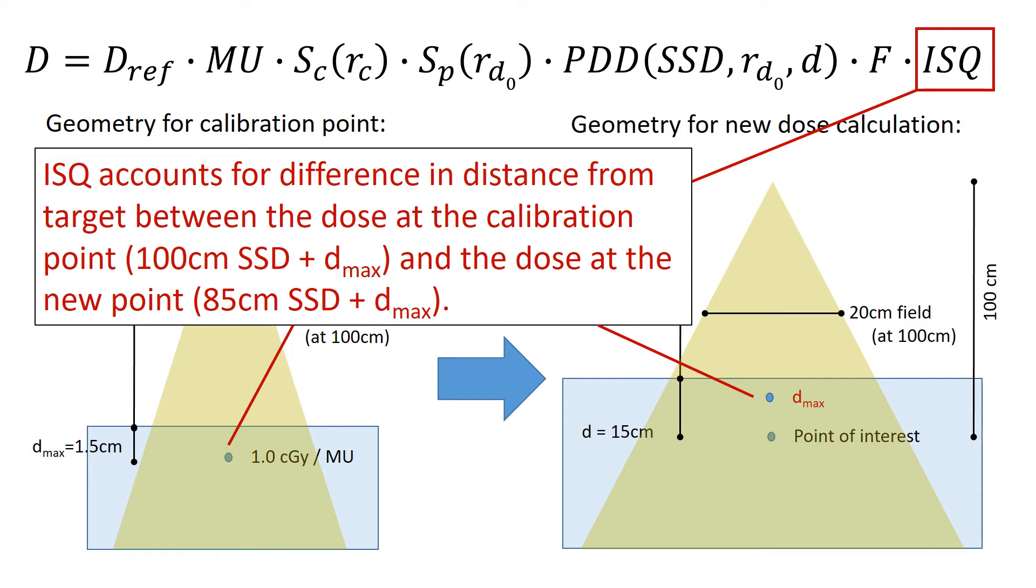And so the inverse square accounts for the difference in the distance from the target between the dose at the calibration point, that's 100 cm SSD plus D max, and the dose at the new point, which is going to be the new point that you start at from your PDD.